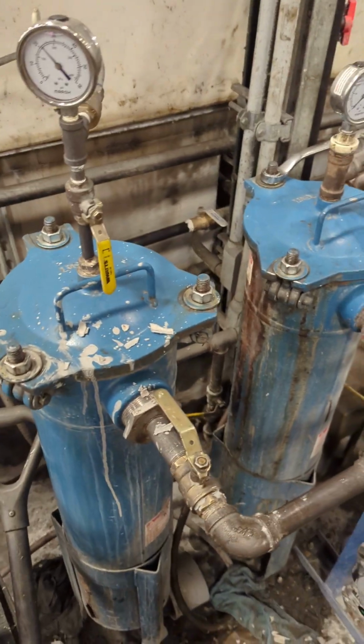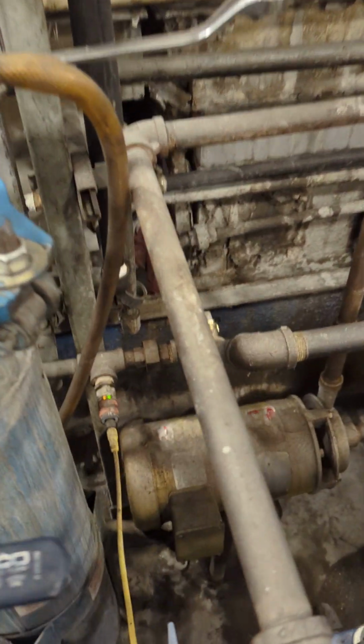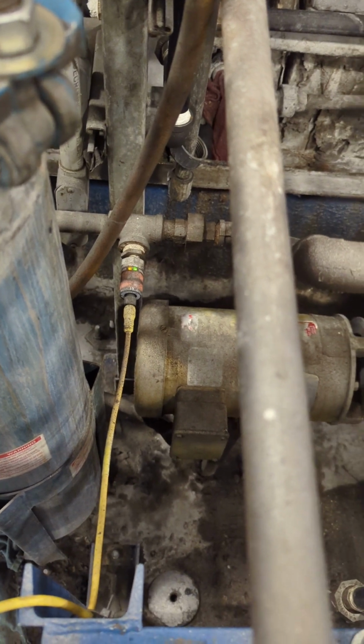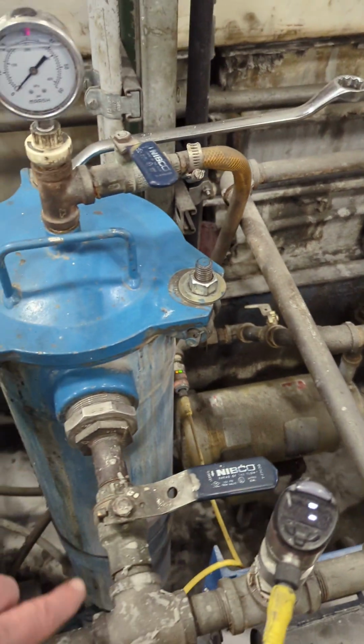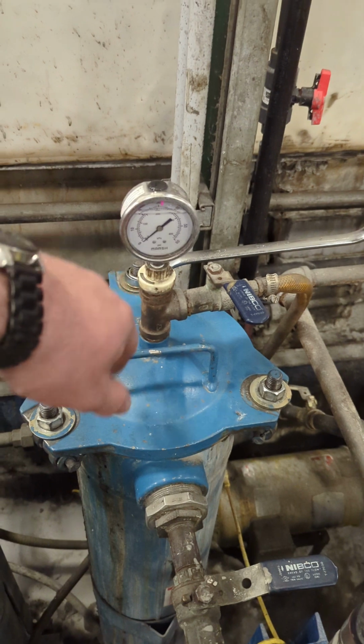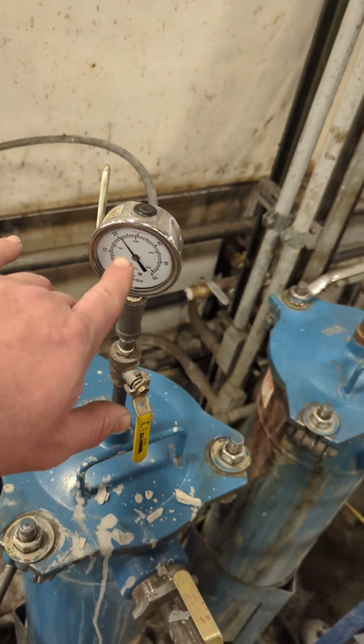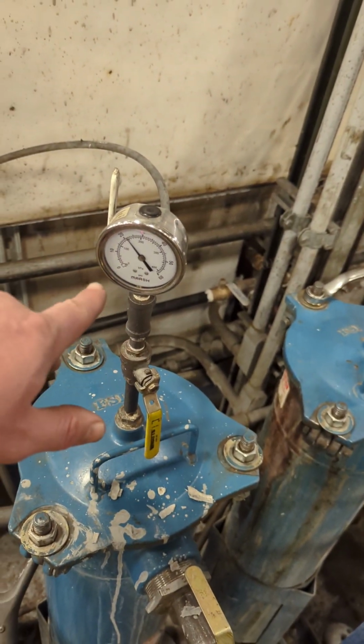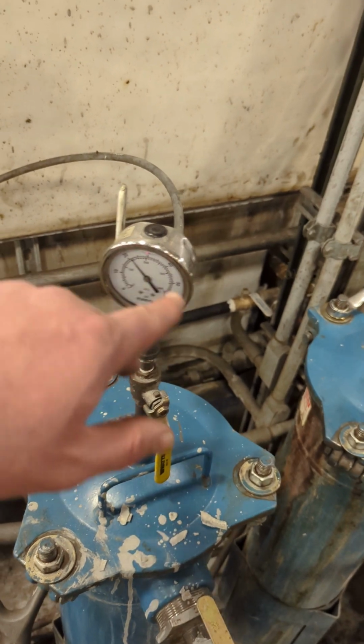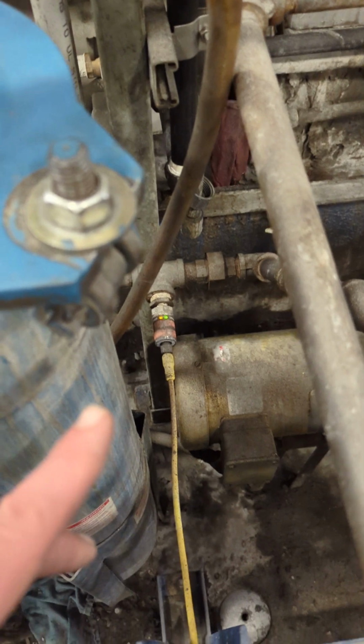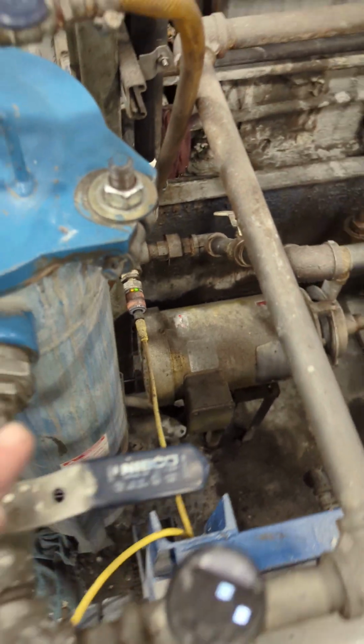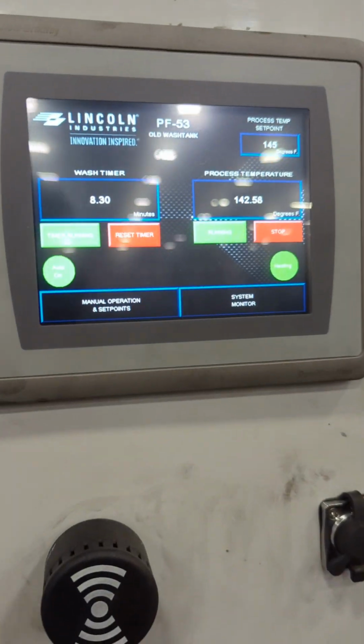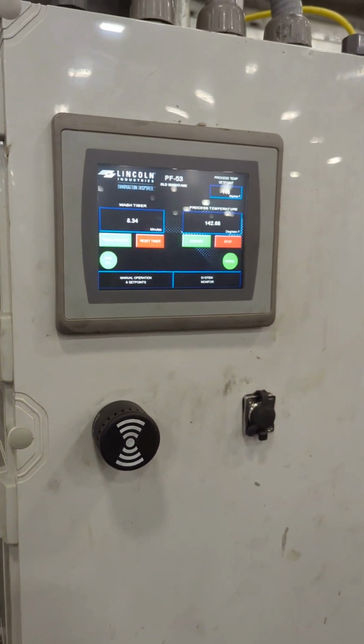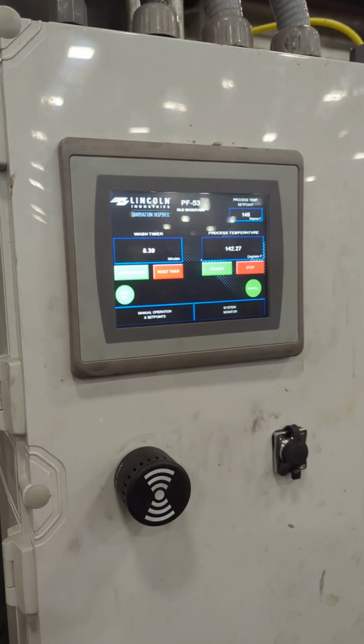Once these filters get full, I set an alarm. What I use is this switch. We use pressure differential. There's a switch back there. As the high side, the supply side, reaches 30 psi on the gauge, that's a full filter for me. So the low side will be putting out about 7.5 psi. And that's when that switch trips, and it'll shut down the recirculation pump and the heater bank, and it'll alarm out up on the control console for the operators, so they know when to switch them over.